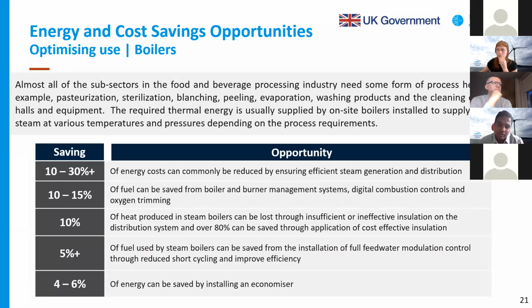As we have seen previously, boilers provide the thermal energy that is a significant driver for much of the processes in the food and beverage industry. So you can see that efficient boiler operation and efficient steam distribution system saves around 10 to 30% of the energy consumption. So we're talking about optimal loading of boilers, distribution systems with effective insulations in place, appropriately functioning steam traps, and then appropriate condensate recovery system in place.